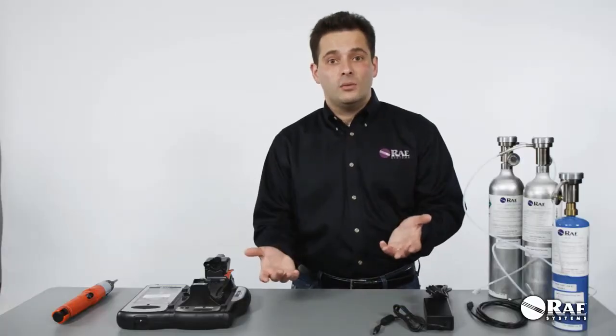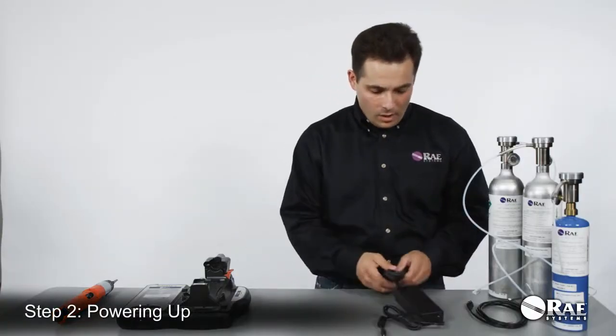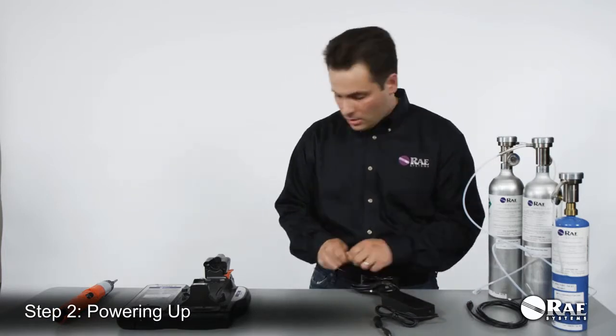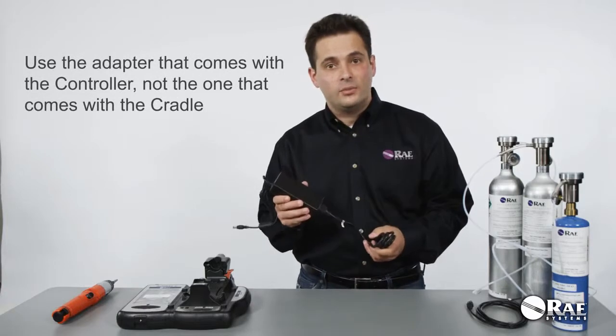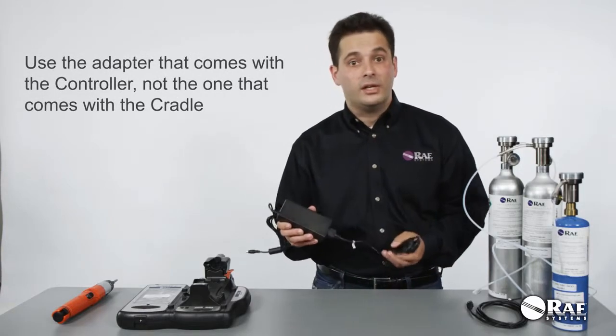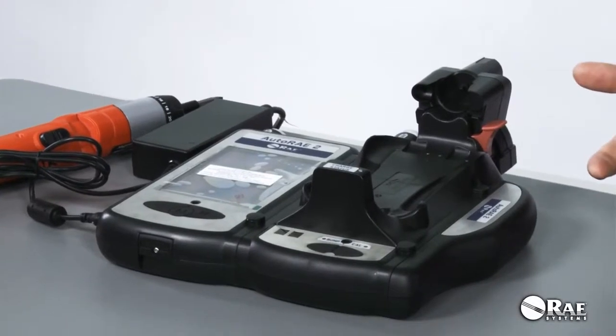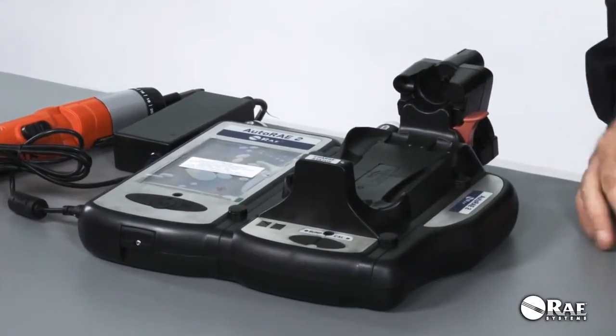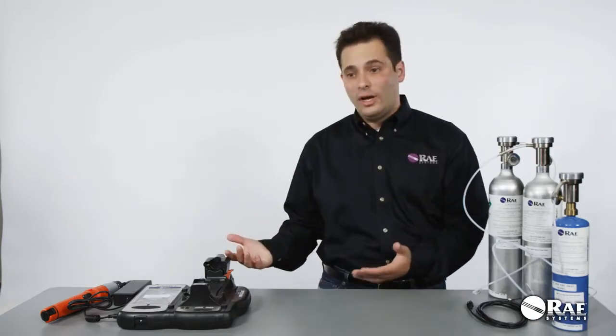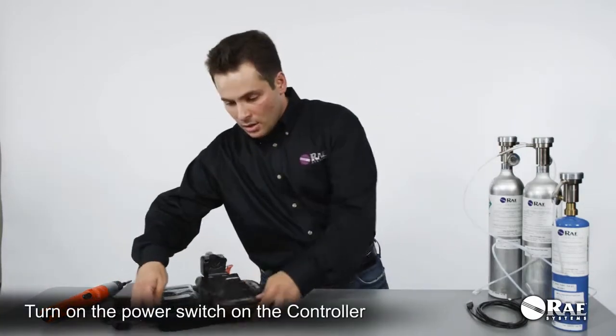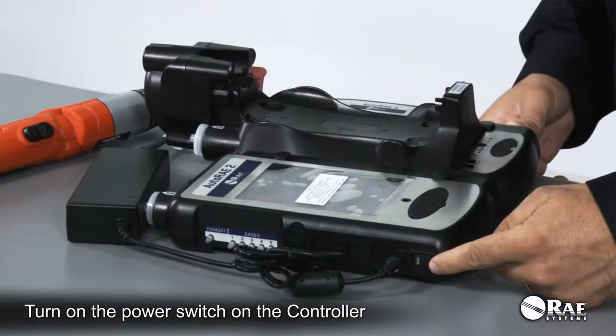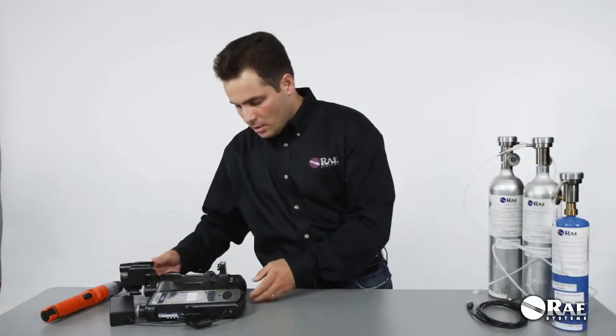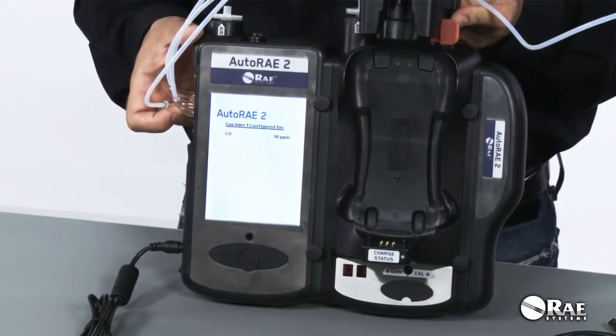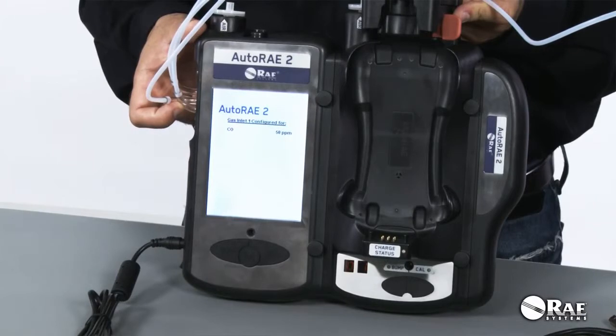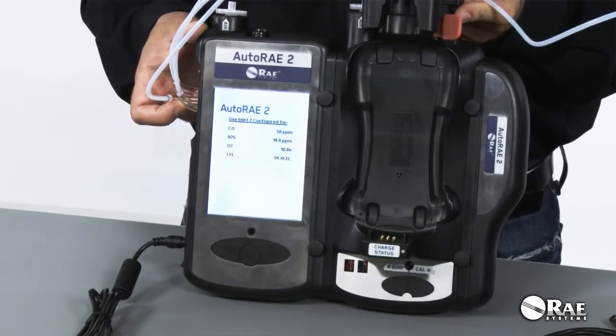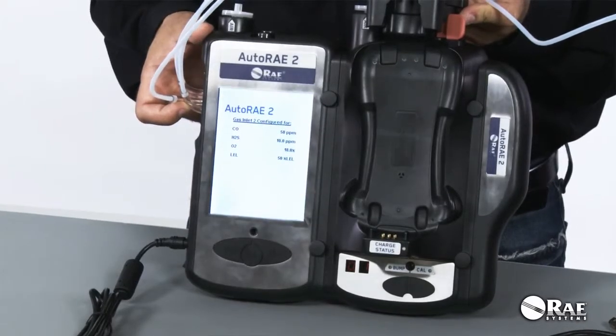Next, in order to prepare the system for calibration or bump testing, we're going to power it on. Once again, we're going to use the large AC adapter that comes with the controller, not the AC adapter that comes with a cradle. Unlike a standalone cradle, a controller-based system has a power on-off switch. So in order to turn the system on, I need to actually turn on the switch, which is located at the bottom left corner of the controller. So the system powers on. You can hear the controller pump turn on. And then once the system completes its power cycle, it's going to be ready for use.